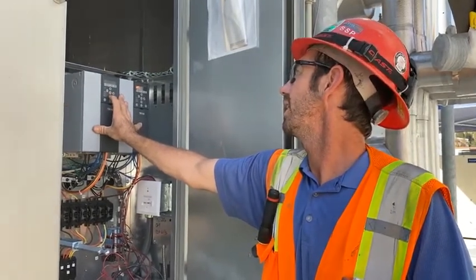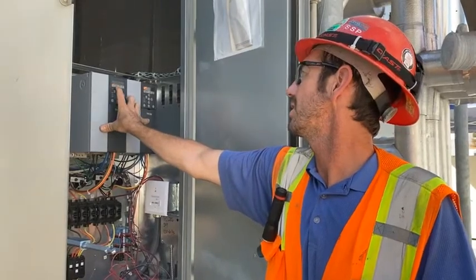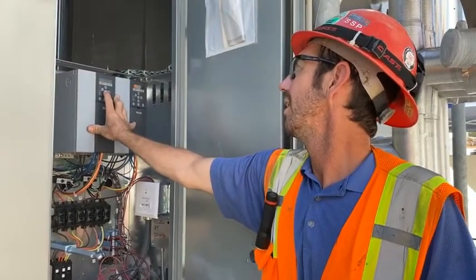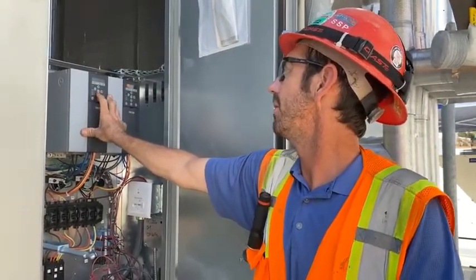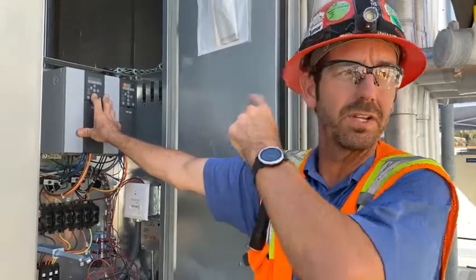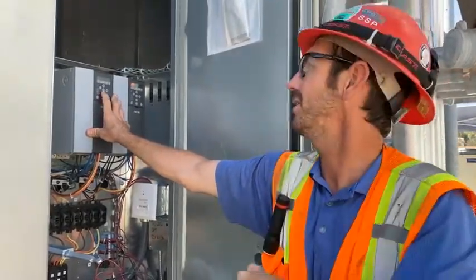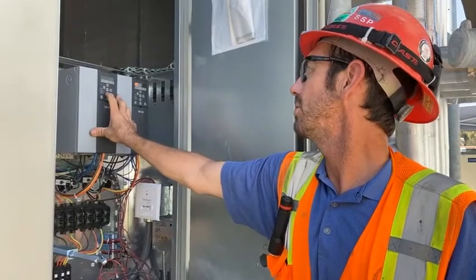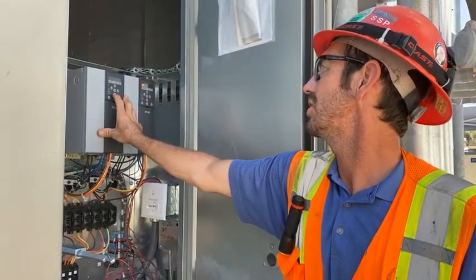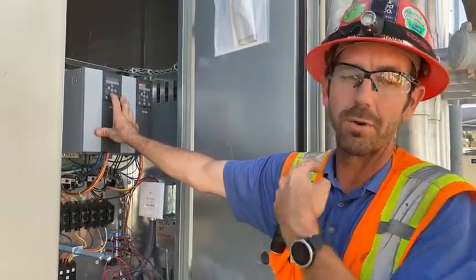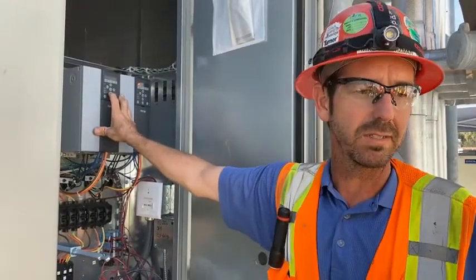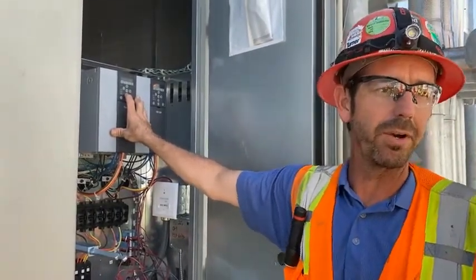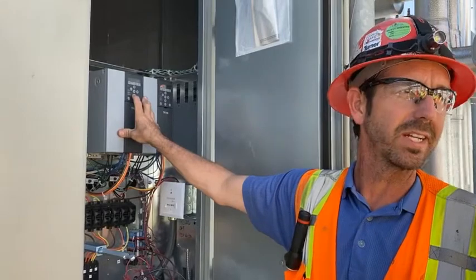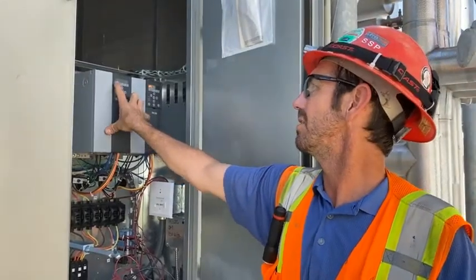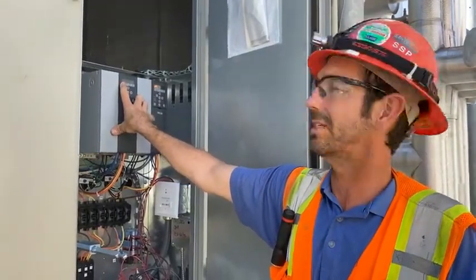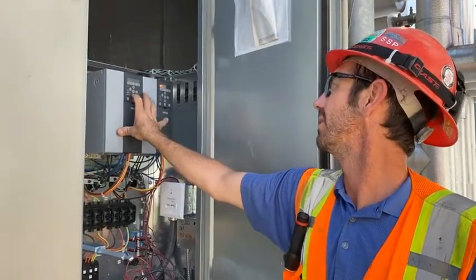Load and motor is where motor data is, 1-2. That's where you're going to enter the data of the motors. Remember, this one is different because we're using the front panel information. We have horsepower, we have the voltage, where the motor frequency is still 60 hertz. It's still a 60 hertz motor, even though we're operating above 60 hertz. I'll get into that in a second. So it's the hertz range of the motor itself that we're looking at right now.